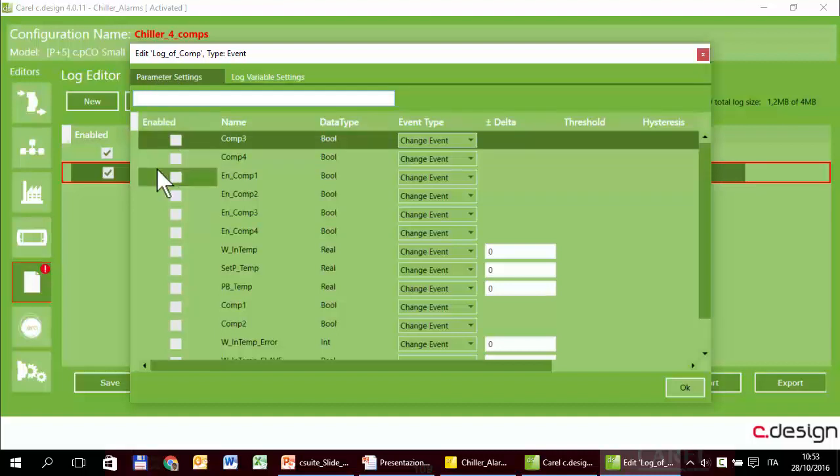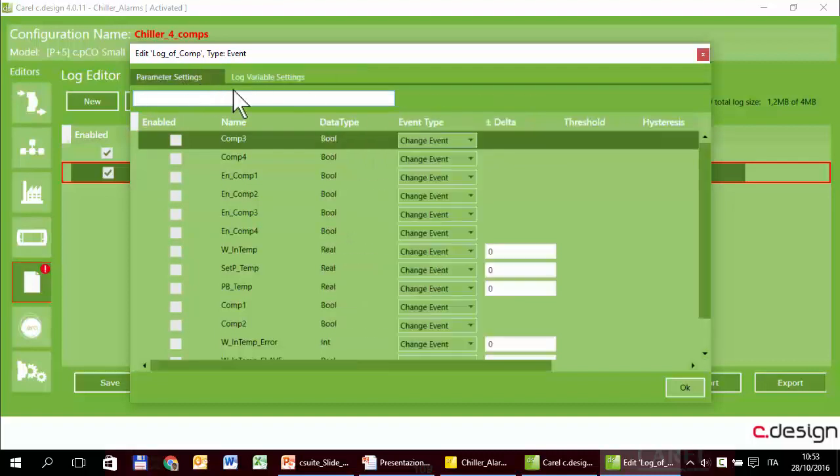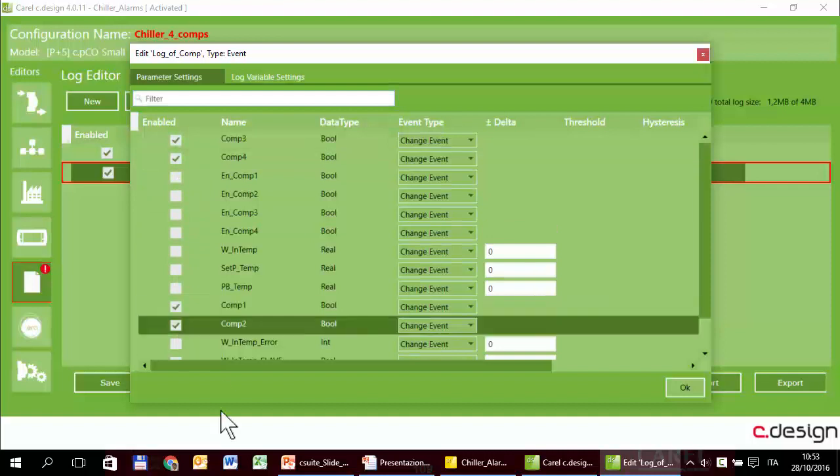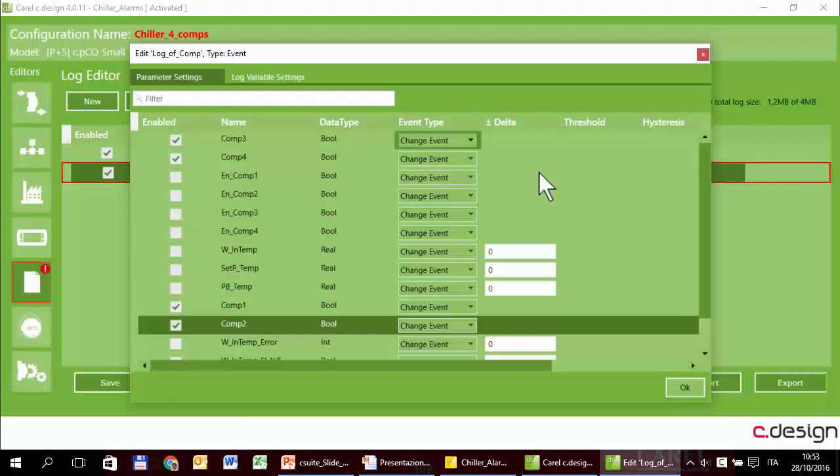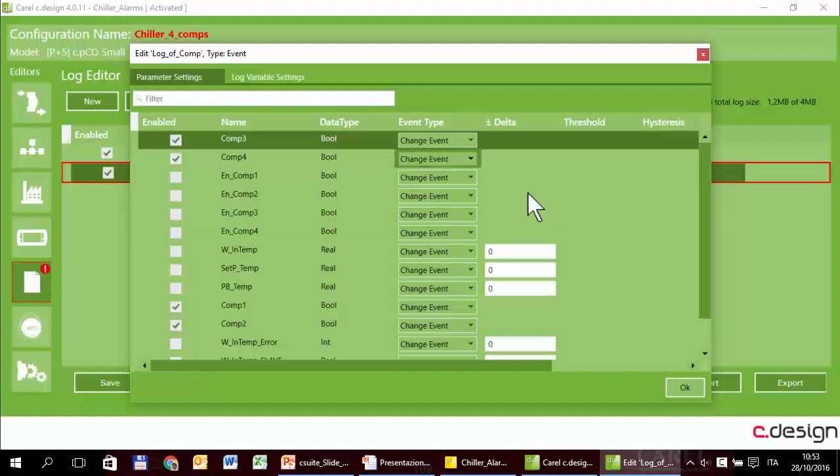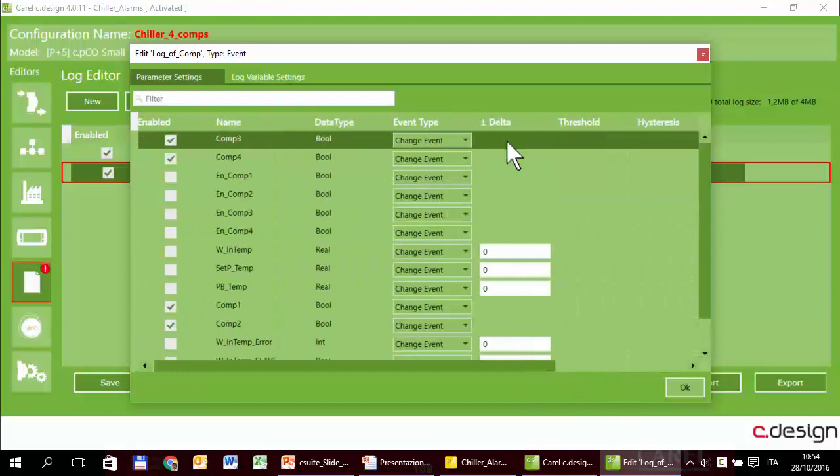So when the variables that will be indicated here, selected here, will be recorded. We want to record the compressor status, so the triggers are the four variables representing the compressors. When one of these variables change, there are two options: change or alarm. Alarm is very particular, and I leave you to read the manual to understand how it works. Typically we use the change event. You can see that for the boolean variables, there are no other options in this column.